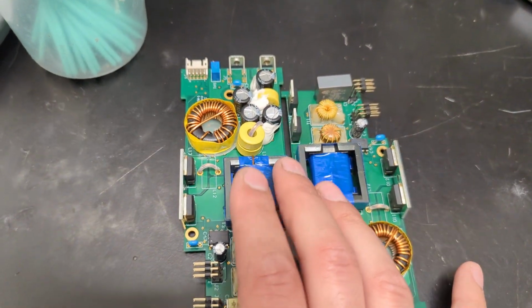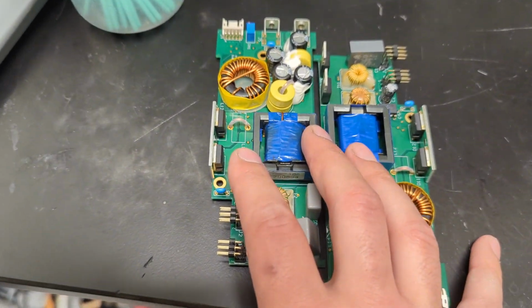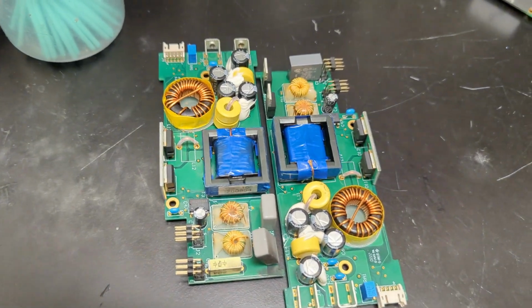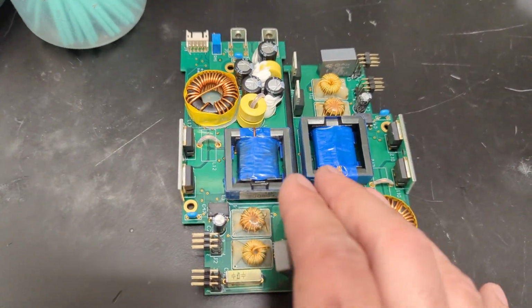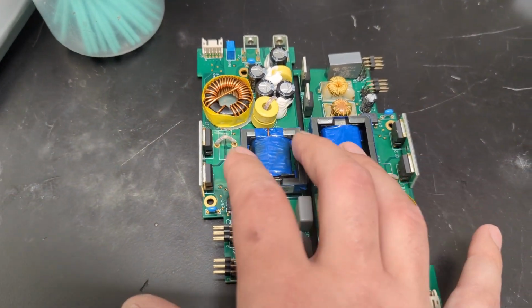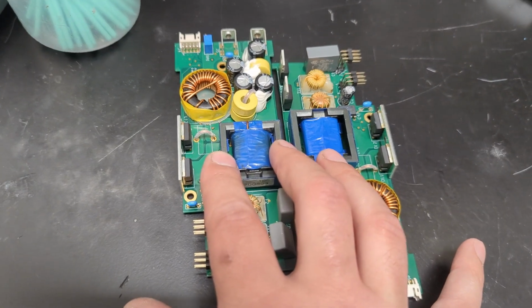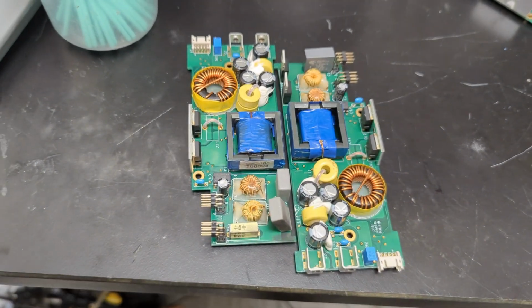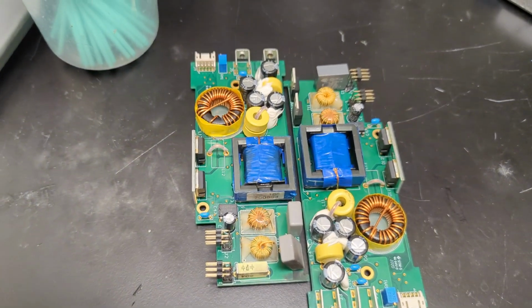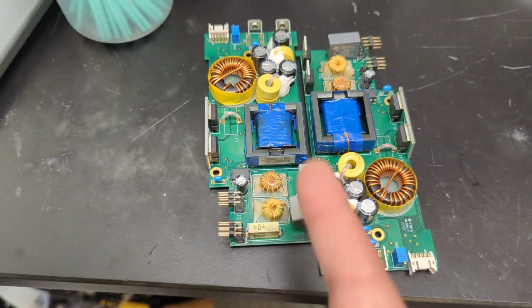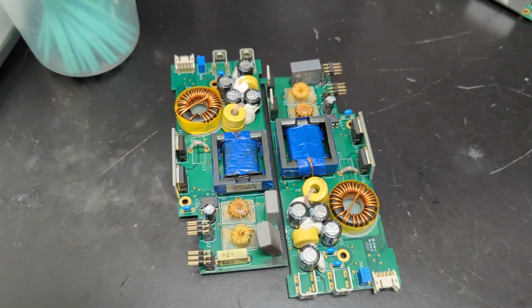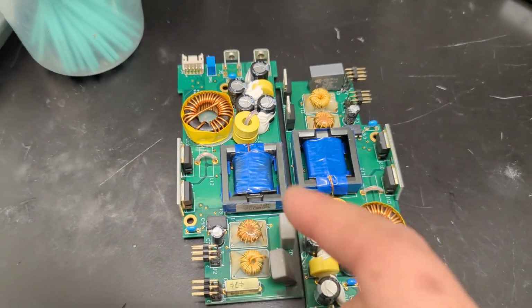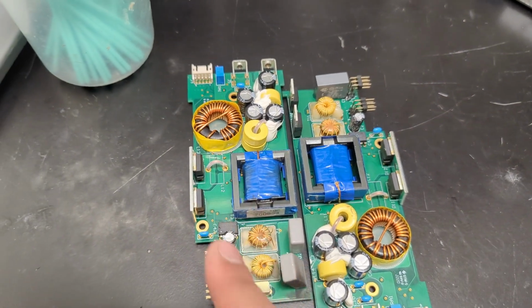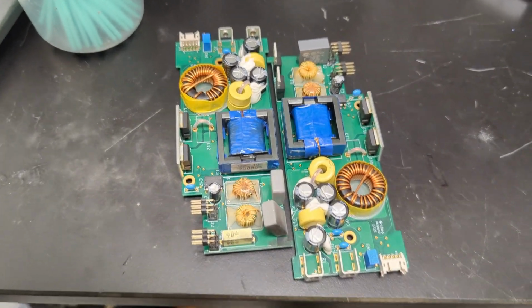That started making me think there must be - well, I shouldn't say must, because I'm not 100% sure - but it almost looks like there could be some internal degradation on this transformer. Once you get up to a high enough current, either a short within a winding or a short across primary and secondary, some current leakage, could be causing these MOSFETs to short.